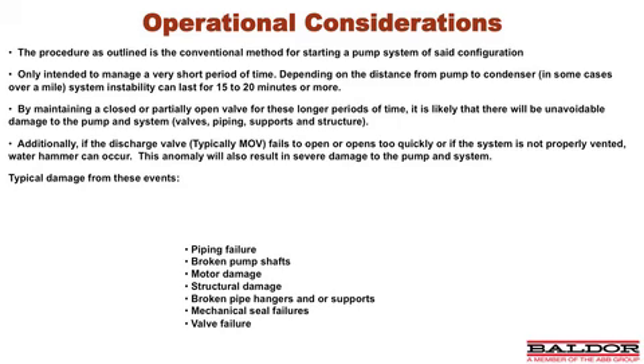However, in some configurations, this startup duration may last for 15 to 20 to 45 minutes in some cases. By maintaining that closed or partially open valve for these longer periods of time, it is likely that there's going to be unavoidable damage to the pump and system.